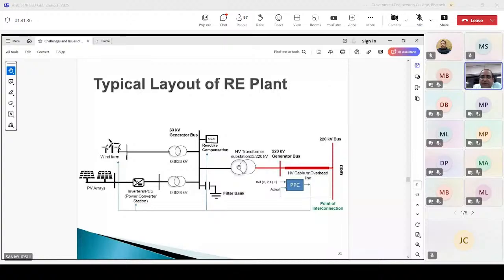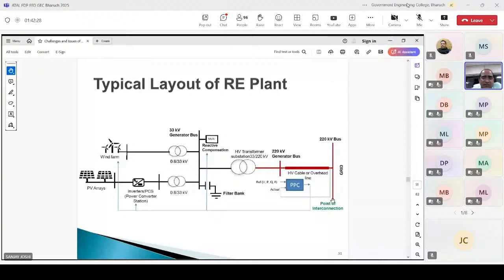Then there is a step-up transformer from 33 to 220 kV. So this is a substation, right? This bus and this transformer might be at the same location. Then the 220 kV generator bus. This grid is very far from this 220 kV bus, so you require an HV cable or overhead line, right? This PPC is nothing but the power plant controller, right? From here, this grid voltage is given to the PPC, and the reference voltage, active power, reactive power, and frequency are given to the PPC, right? The output signals of the PPC are given to the reactive power compensation, the VSC connected to the PV array, and the VSC of the wind farm, right? This 220 kV bus is known as the point of interconnection. So this whole system is a plant of RE.